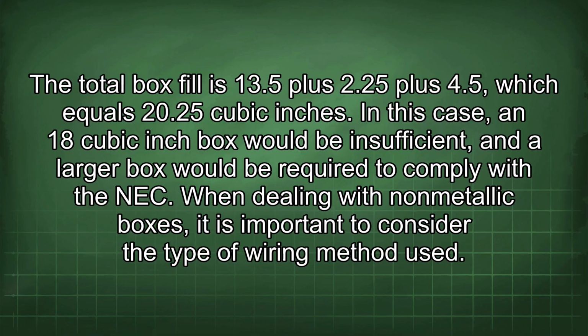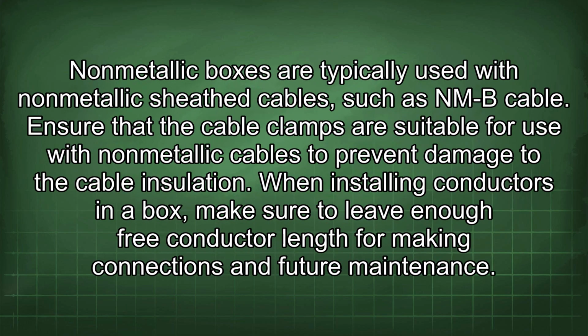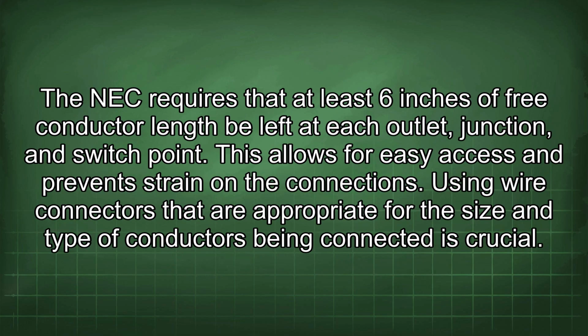In this case, an 18 cubic inch box would be insufficient, and a larger box would be required to comply with the NEC. When dealing with non-metallic boxes, it is important to consider the type of wiring method used. Non-metallic boxes are typically used with non-metallic sheath cables, such as NM-B cable. Ensure that the cable clamps are suitable for use with non-metallic cables to prevent damage to the cable insulation. When installing conductors in a box, make sure to leave enough free conductor length for making connections and future maintenance. The NEC requires that at least 6 inches of free conductor length be left at each outlet, junction, and switch point. This allows for easy access and prevents strain on the connections.